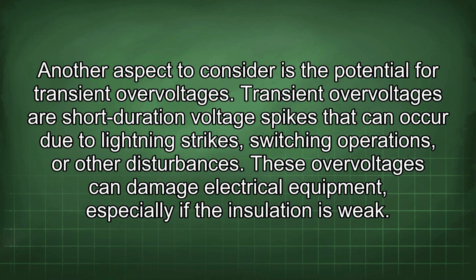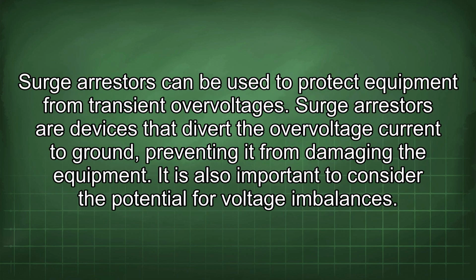Another aspect to consider is the potential for transient overvoltages. Transient overvoltages are short-duration voltage spikes that can occur due to lightning strikes, switching operations, or other disturbances. These overvoltages can damage electrical equipment, especially if the insulation is weak. Surge arresters can be used to protect equipment from transient overvoltages. Surge arresters are devices that divert the overvoltage current to ground, preventing it from damaging the equipment.